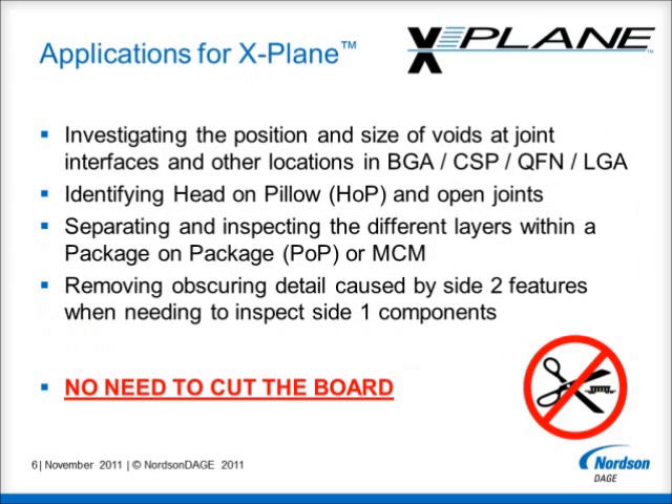X-Plane provides enhanced inspection capabilities for many of the most challenging applications in the electronics industry. It can be used to investigate the position and size of voids, joint interfaces and other critical locations in BGAs, CSPs, QFNs and LGAs, amongst others. It can be used to identify head-in-pillow defects and open joints in BGAs.